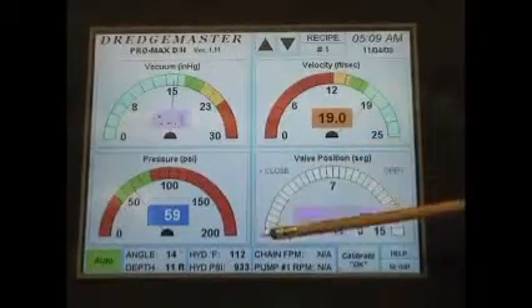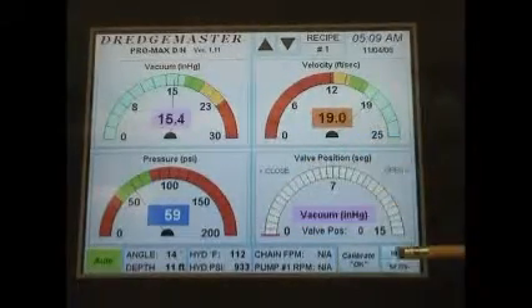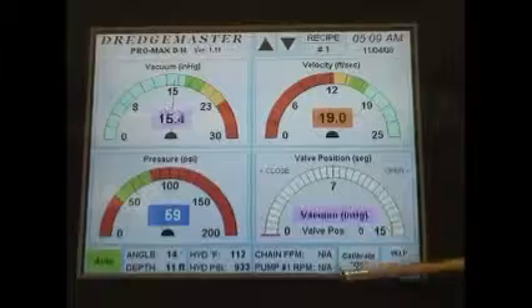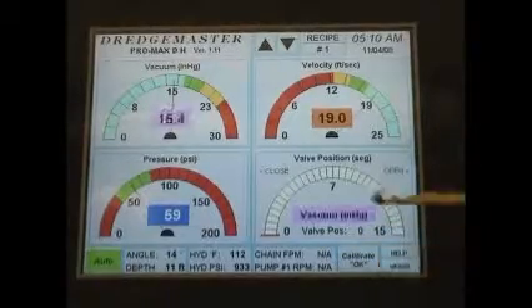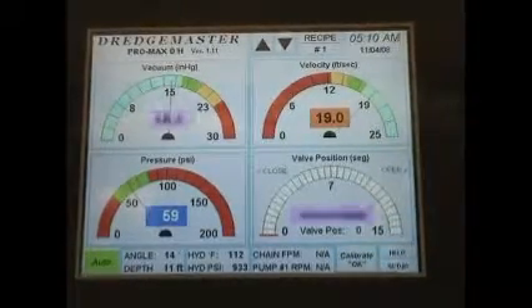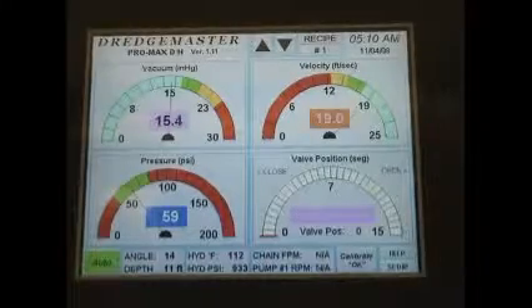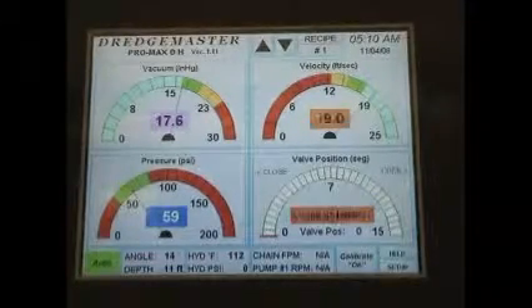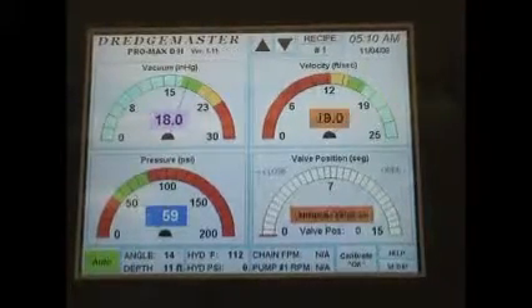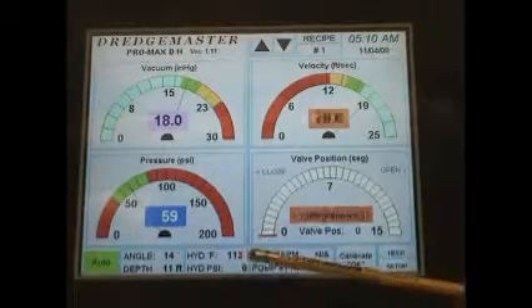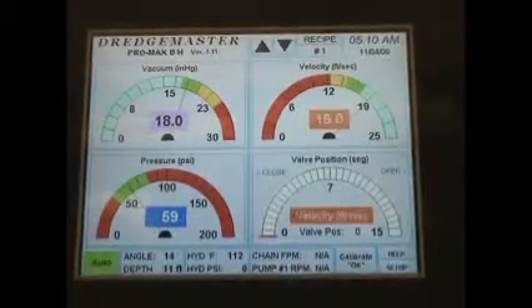Once the valve is closed all the way, as you can see, now our calibration is okay. Now the operator can go back to pumping. This procedure of calibration is only going to happen once our oil temperature has changed more than 30 degrees.